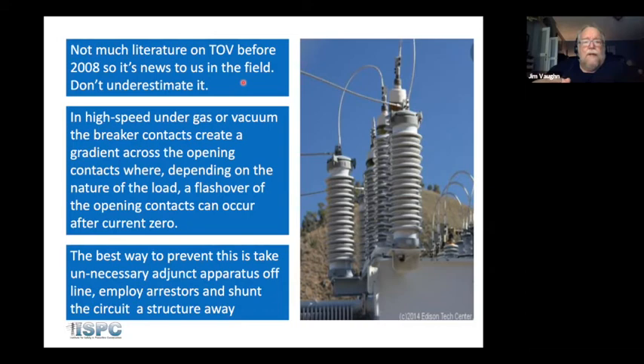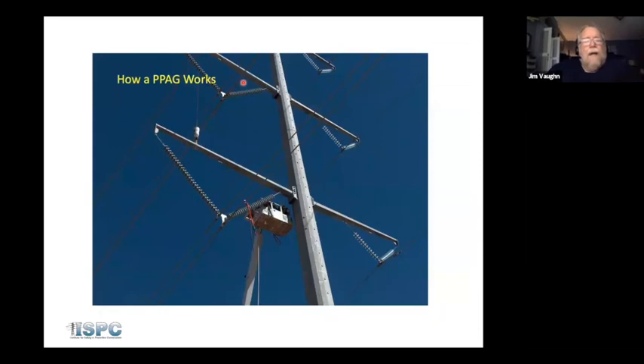But the problem is that these are usually only in the substations, not out on the circuit. And if the arrester is not in the opportune position to be exposed to the TOV, then it may not be very effective. It actually needs to be between the switch and the circuit in order to be effective. So there's research that's being done now and being developed. Now, when we talk about the PPAG, the portable air gap, if you've been building transmission for a while, you know that you have some wood strain, insulating strain conductor on down guys. And you also remember that a number of them were built with an electrode or a piece of conductor that sticks up at both ends.